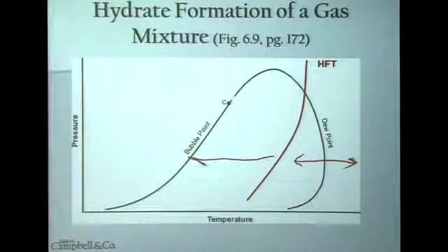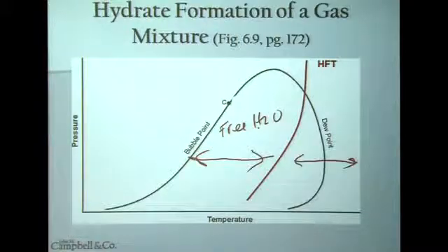However, if your system temperature is colder than the hydrate formation temperature, and if you have free water in your system, you run the danger of forming hydrates. So if you find yourself operating to the left of the hydrate formation temperature curve and you have free water in the system, you need to do something.